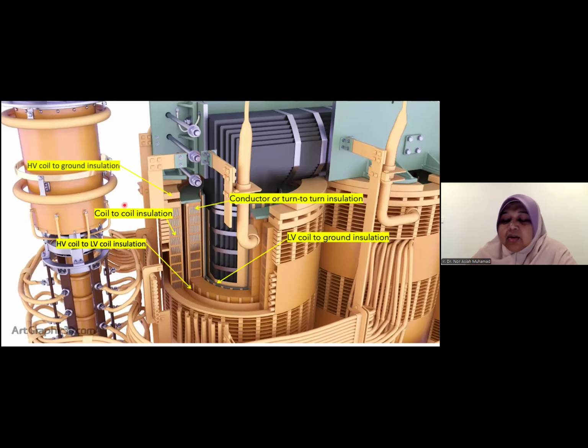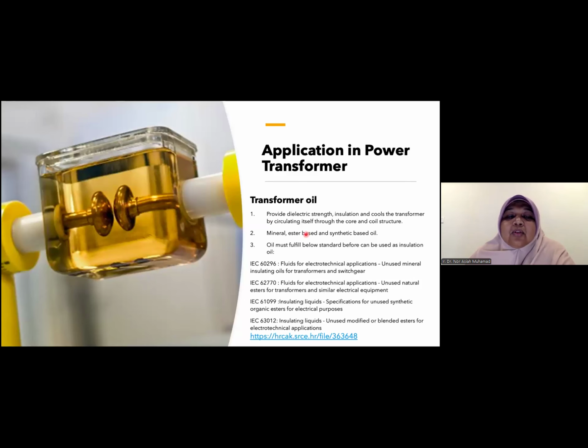If they are oil immersed transformers, we will use transformer oil inside the tank as another level of insulation material, and also as a heat dissipation material. The oil provides dielectric strength, insulation, and cools the transformer by circulating itself through the core and coil structure. There are mineral base, ester base, and synthetic oil base. In the last 20 years, most of the equipment used mineral oil. But since the late 1990s or 2000 there has been new ester base. Actually, ester base is not new. It existed before mineral oil but was stopped. Then about 30 years back, they came back to ester base.